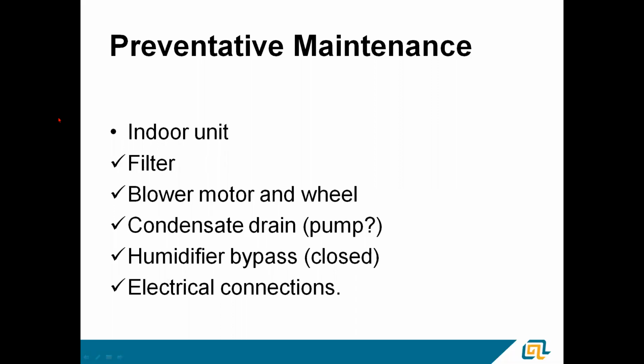At the indoor unit, and I don't consider this a comprehensive list of things that you would do on a normal clean and check, but these are the things you've got to hit on, even if you're going out there on just a regular service call. Check the filter, check the blower motor and wheel. One of the things I always look for on the blower wheel is if it's caked and loaded with dust and dirt and debris. You have to believe that the underside of that coil is looking about the same. So if you've got a really dirty blower motor and wheel, you may have to pull a coil and at least inspect it. Condensate drain, make sure it's clear and free flowing.